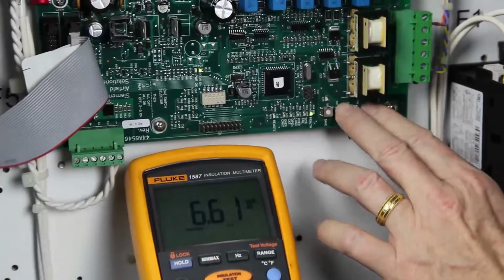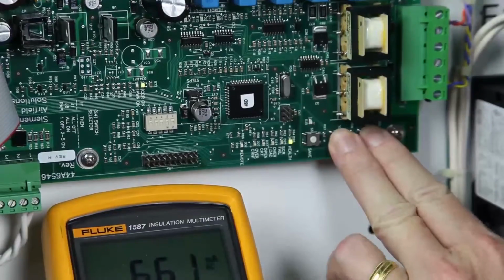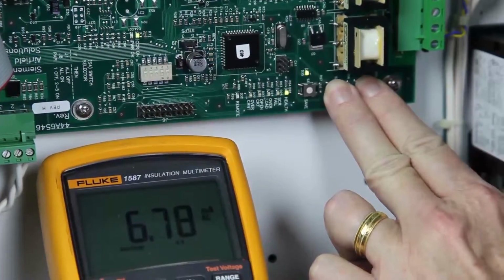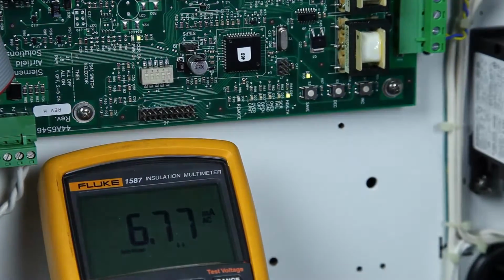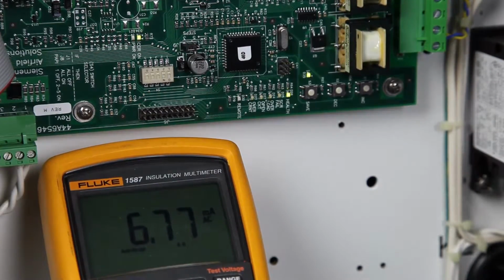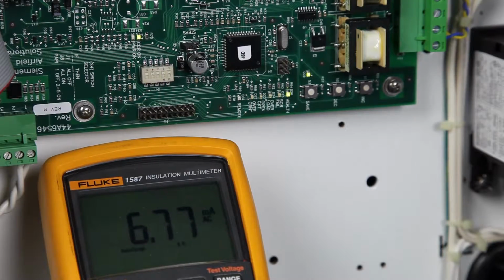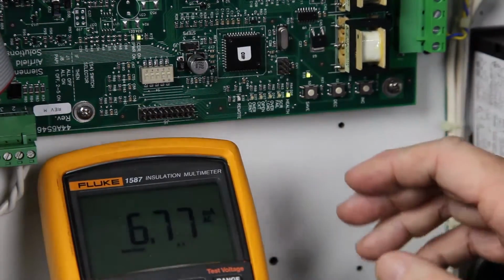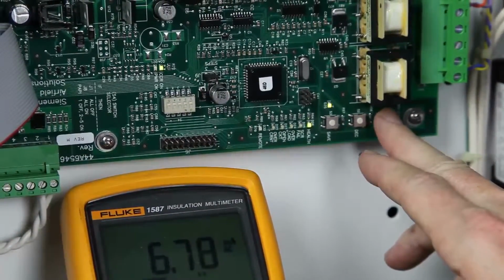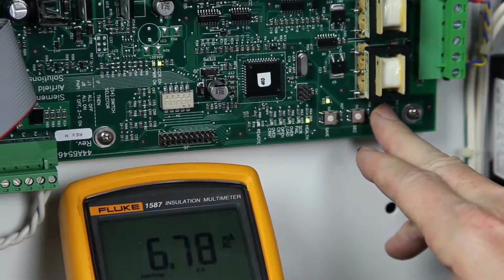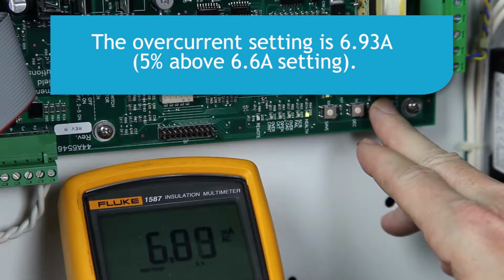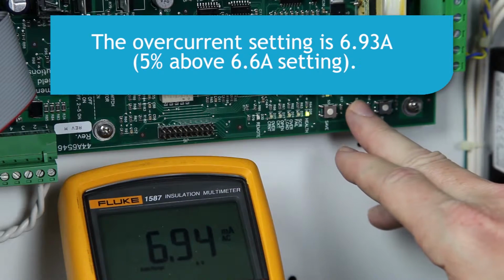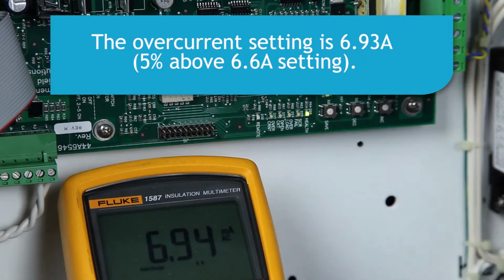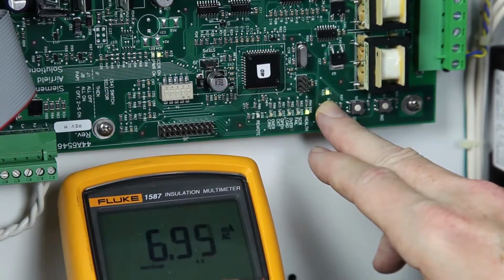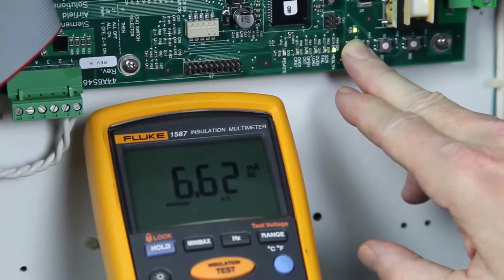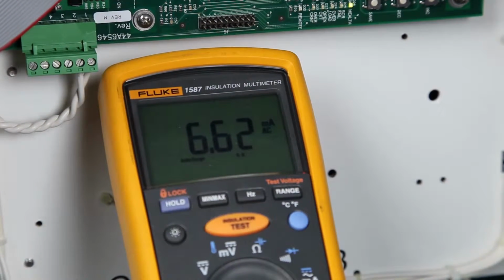Next, press and hold the increase and decrease buttons at the same time for about 3 seconds. Then the LED next to the save button will illuminate, indicating that you are in the overcurrent adjustment mode. Note that the CCR output current will increase to the level previously set as the overcurrent level. Next, you want to use the increase or decrease buttons to set the new overcurrent setting. In this case, we want to set the overcurrent to 6.93 amps, which is about 5% above the 6.6 amp setting. Then press and hold the save button. The LED will extinguish and the CCR will revert to the normal operating mode.